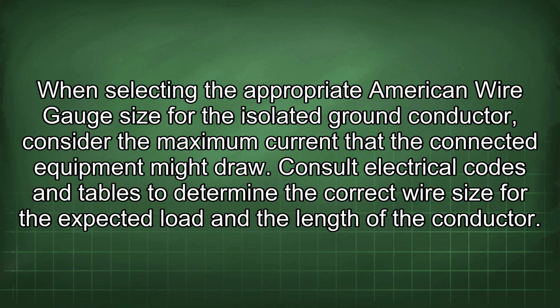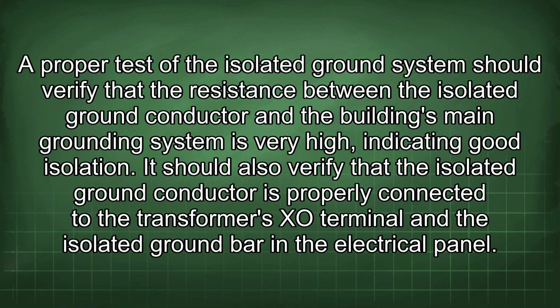When selecting the appropriate American wire gauge size for the isolated ground conductor, consider the maximum current that the connected equipment might draw. Consult electrical codes and tables to determine the correct wire size for the expected load and the length of the conductor. A proper test of the isolated ground system should verify that the resistance between the isolated ground conductor and the building's main grounding system is very high, indicating good isolation. It should also verify that the isolated ground conductor is properly connected to the transformer's XO terminal and the isolated ground bar in the electrical panel.